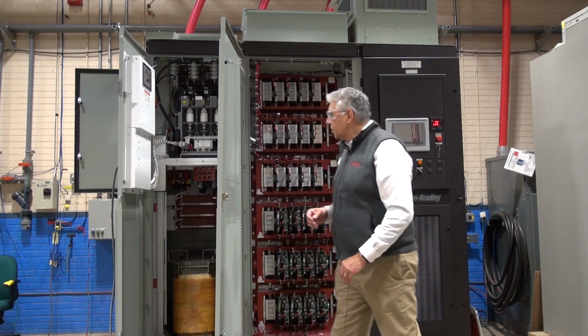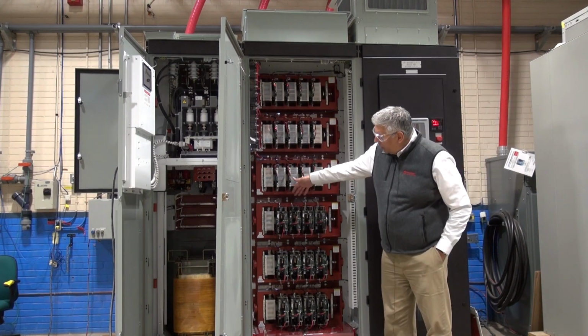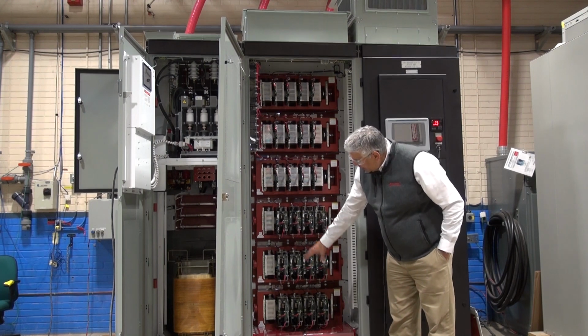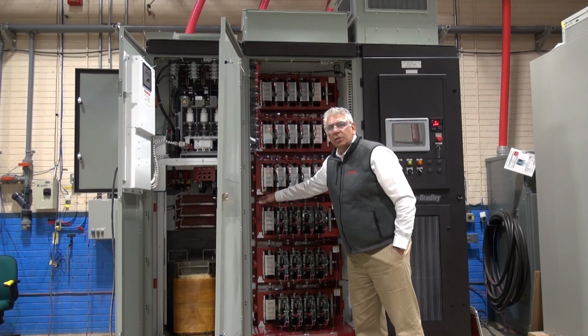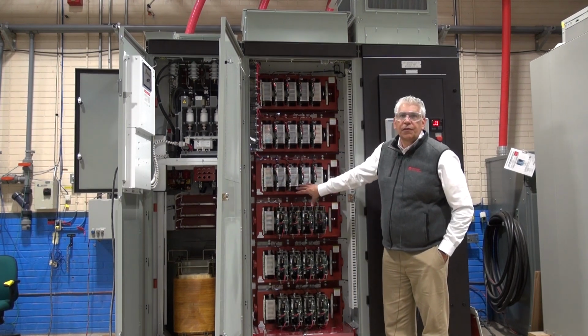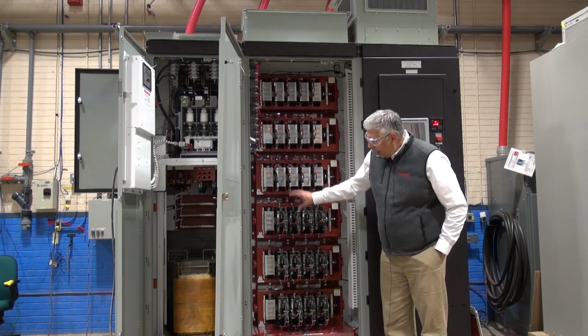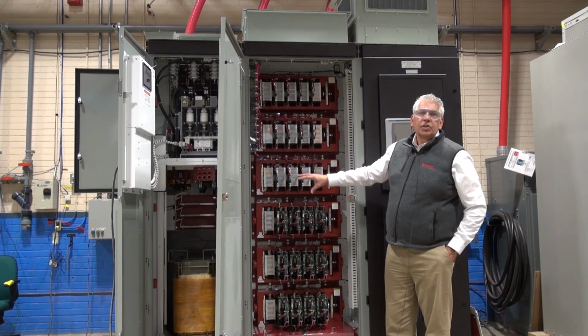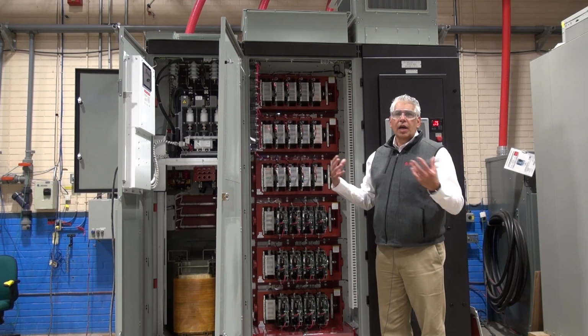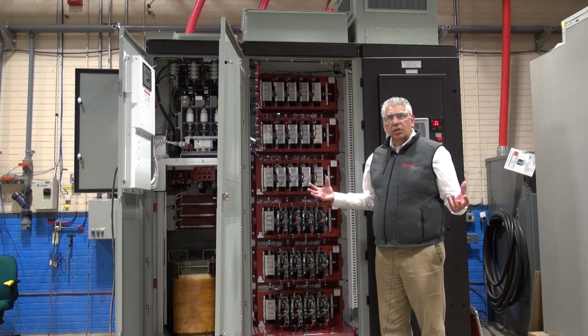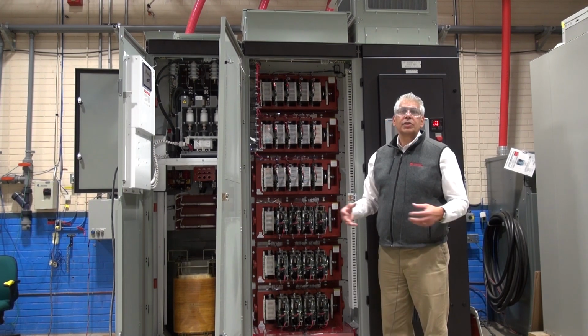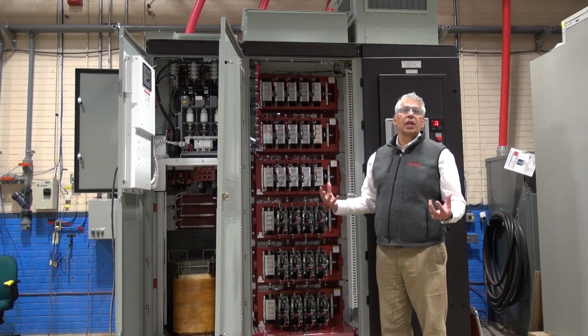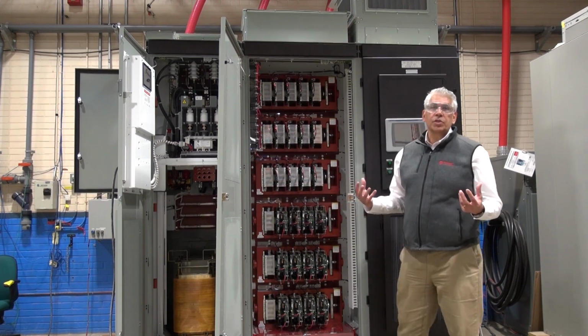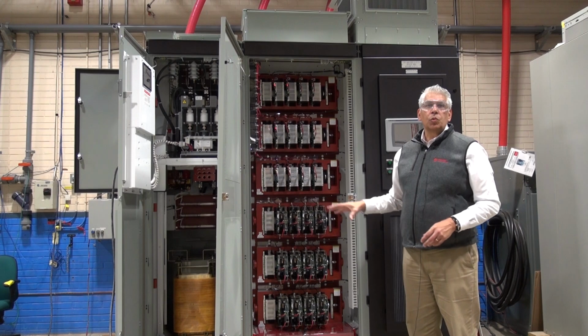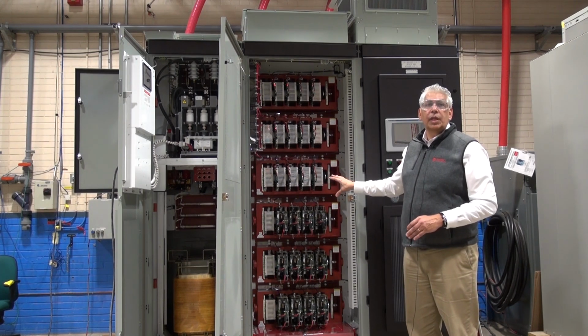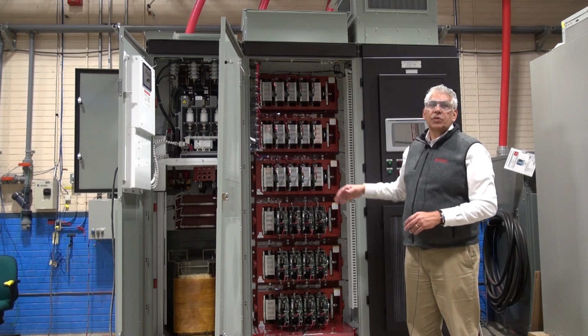So why is that important? There's a couple of benefits you get with an SGCT. So here are the devices. The bottom 3, these red housings, we call power cages, and all the devices in one phase fit in one of these power cages. So this is phase A, B, and C of the rectifier, A, B, and C of the inverter. So a single bridge. You don't have multiple bridges, you don't have a lot of components. It's the lowest component count of any drive topology in the marketplace. Lower component count and higher reliability per component means an extremely reliable package. Many or most of our customers are extremely concerned with uptime, and a low component count with each component having very high reliability delivers that maximum uptime that most of our customers are looking for.